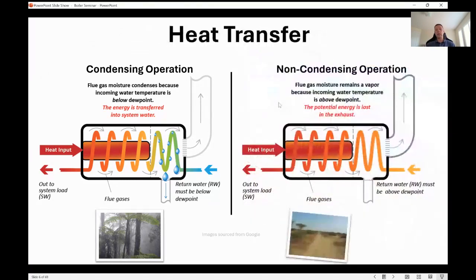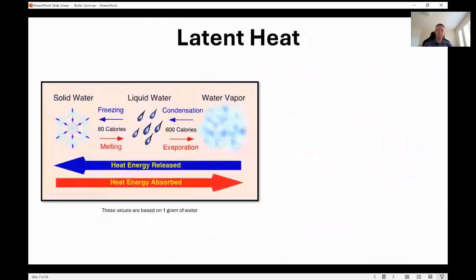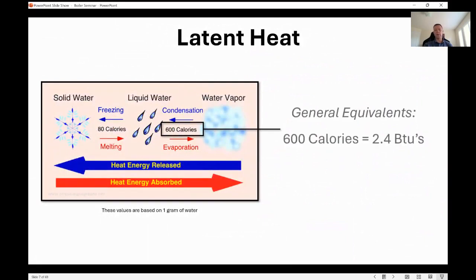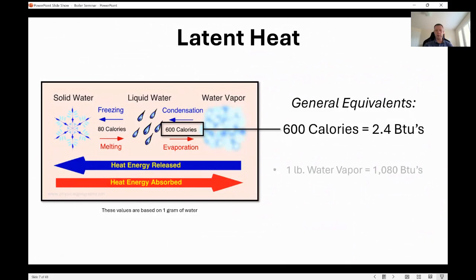If you took that same product and put it in a non-condensing mode, so maybe this unit here, you got 150 degree return water temperature. That return water temperature is going to go into that area where condensation can occur, but you're not going to be condensing there. You still pull heat out of those flue products. You're just not going to pull enough to condense. Then, of course, you're going to go near the burner, and you're going to add more heat into the system there. As I said, it's all about changing state. That is where you're getting that extra efficiency out of it, right?